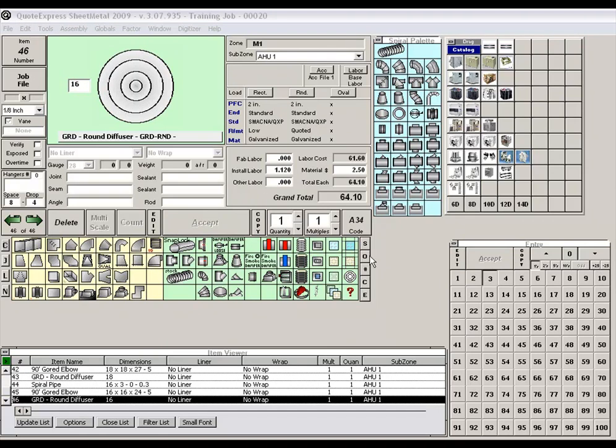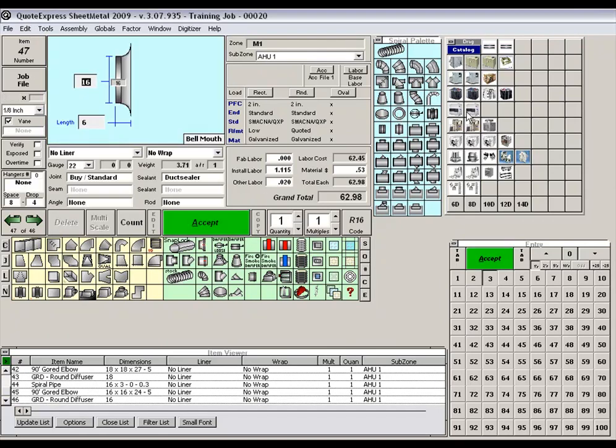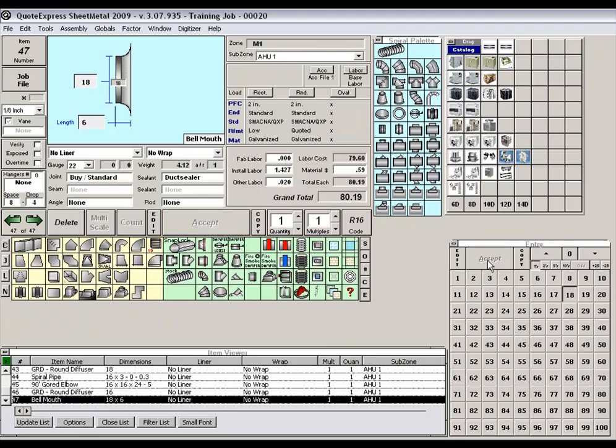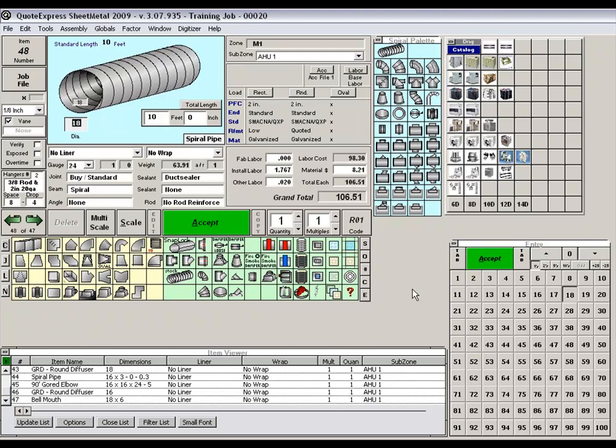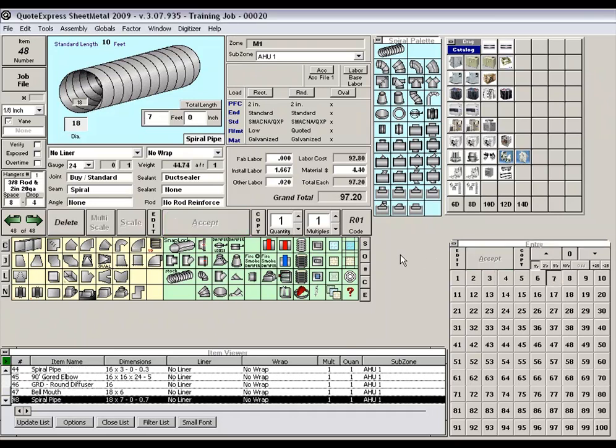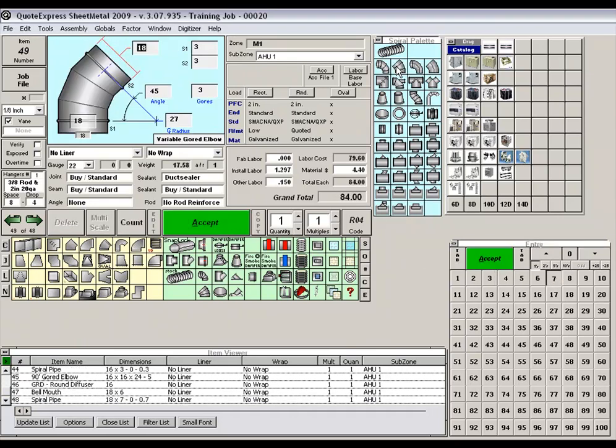There is another round takeoff. We'll begin with the 18-inch diameter takeoff again. Select 18, and then Accept. 7 feet of pipe before a 45-degree elbow. Tab, 7, and then Accept. Now we have a 45-degree elbow, and at this point I'm going to look forward on my print and see that there is another one. So I'll go ahead and put in a quantity of 2.